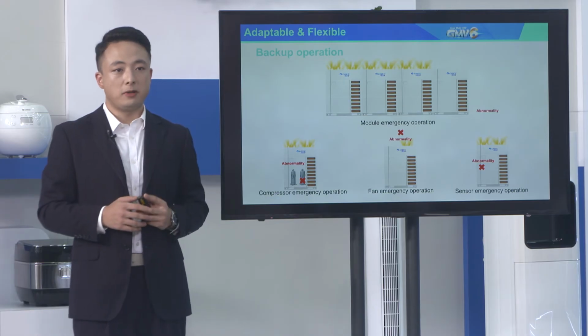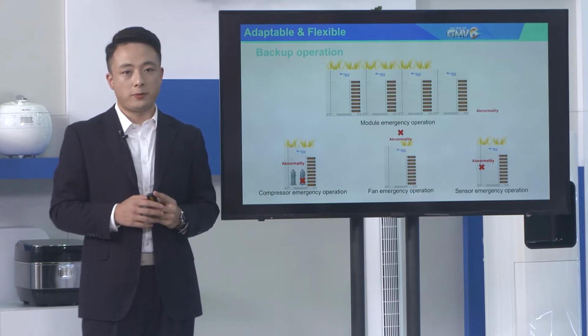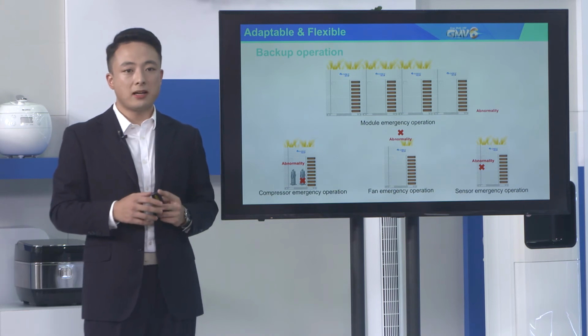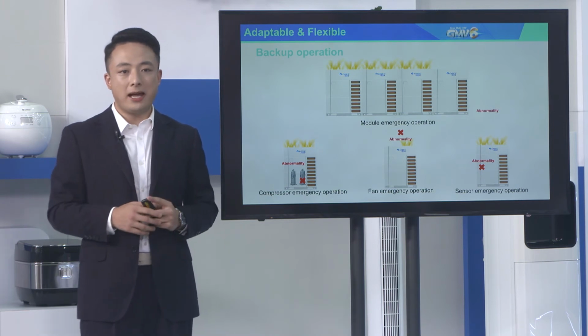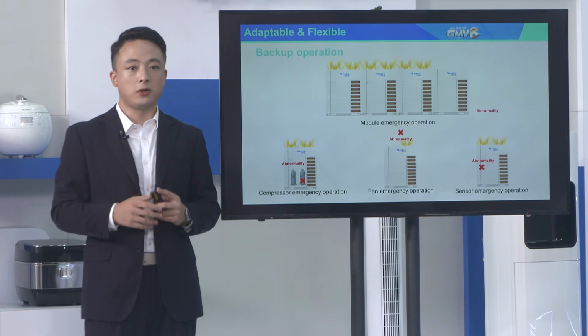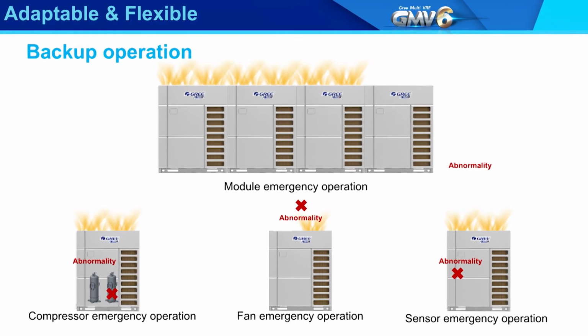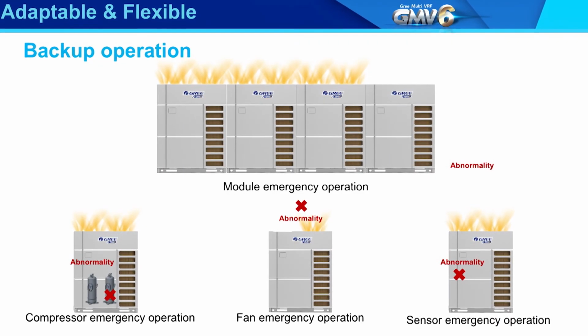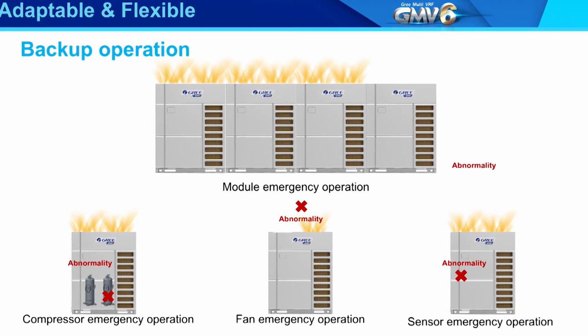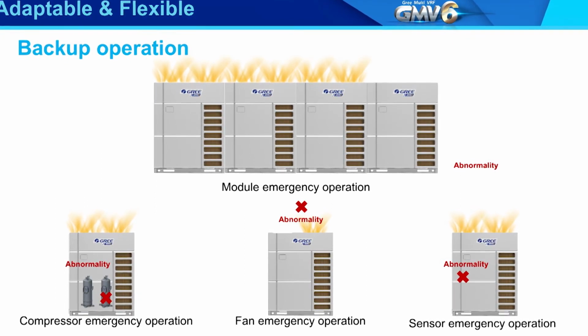VRF units are widely used in different places. When the unit runs abnormally during its operation, it can enter a backup mode to minimize the impact of the abnormality, because of the full backup operation functions of the basic module: compressor, fan, and sensor abnormality.